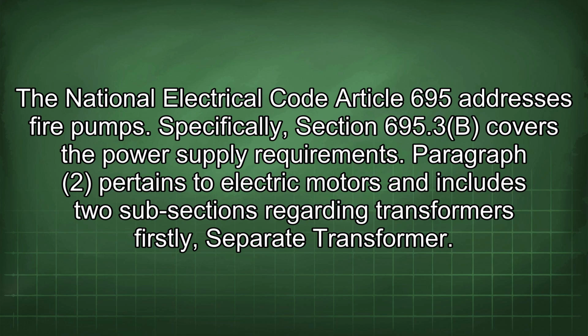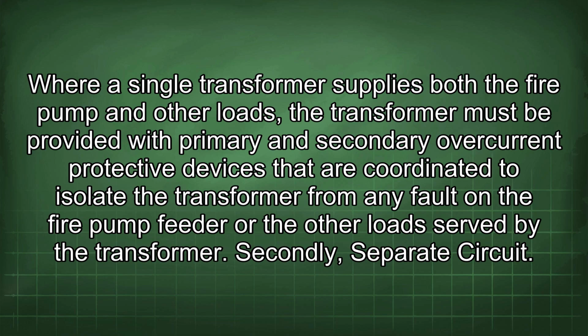Firstly, separate transformer. Where a single transformer supplies both the fire pump and other loads, the transformer must be provided with primary and secondary overcurrent protective devices that are coordinated to isolate the transformer from any fault on the fire pump feeder or the other loads served by the transformer.